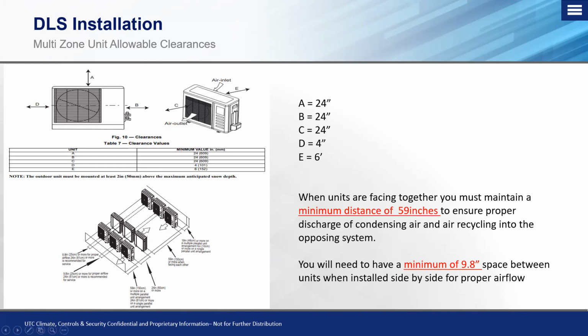It's very important, you see on the back side here, that these units aren't going to face the opposite way, so that they're discharging their condensing air into the back side of the other coils. Come heating season, this causes a lot of issues, especially frosting issues. We've had it happen on an application before, and unfortunately the only thing that we can do is move those units away. So if we have a row application, we need to make sure that the back side of the coils that are facing each other and the discharge side of the outdoor unit are all facing in the same direction. And if they are facing each other in this particular circumstance, we need at least 60 inches to ensure proper discharge air out of the unit so that we're not recirculating anything or causing any operational issues.